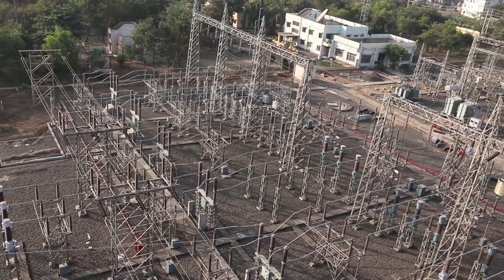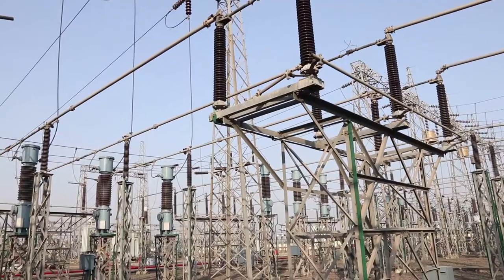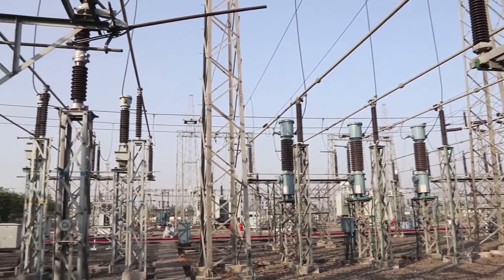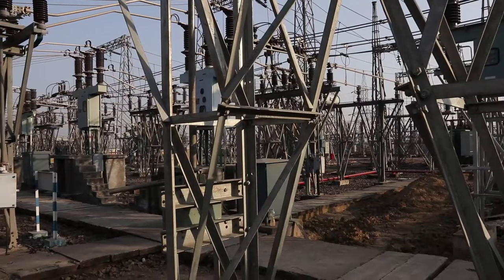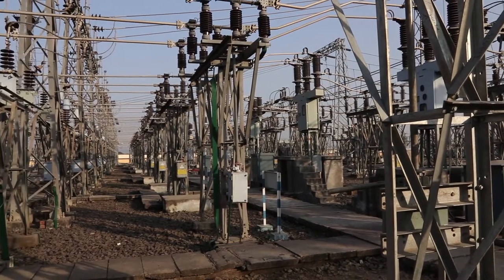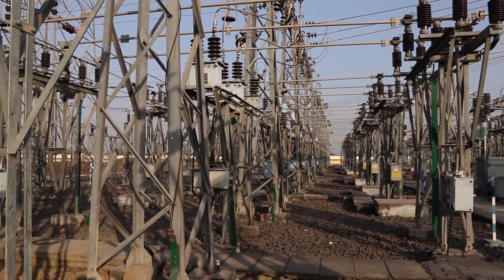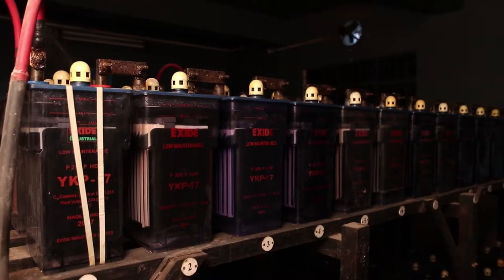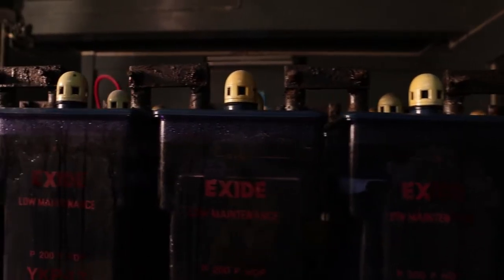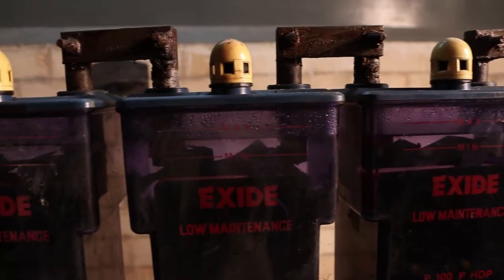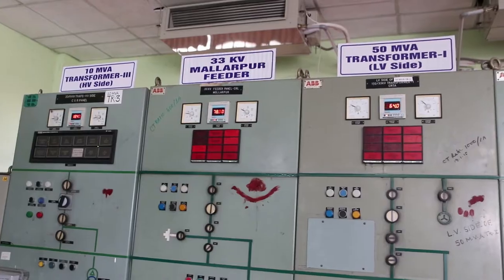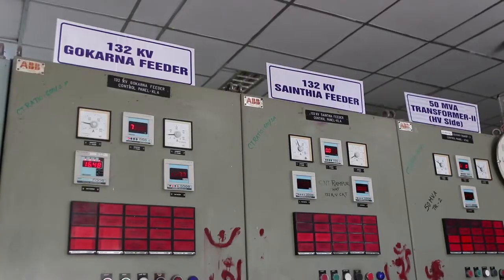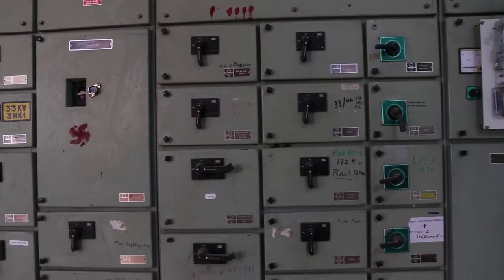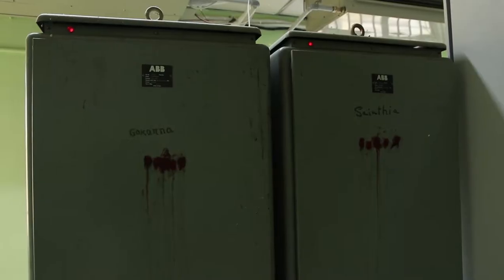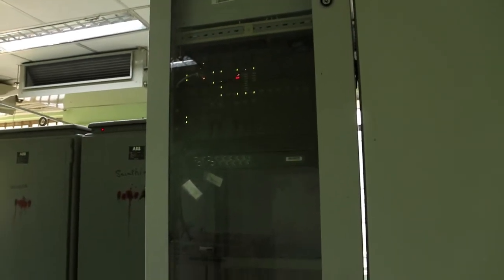Maintenance and activities. Periodic maintenance of all substation equipment, bus, transformers, clamps and connectors are done regularly as per the maintenance schedule in order to achieve more availability and fewer breakdowns. We perform all operational jobs at control room. The entire DC systems are very well maintained at site with timely cleaning, distilled water topping up and specific gravity measurement.